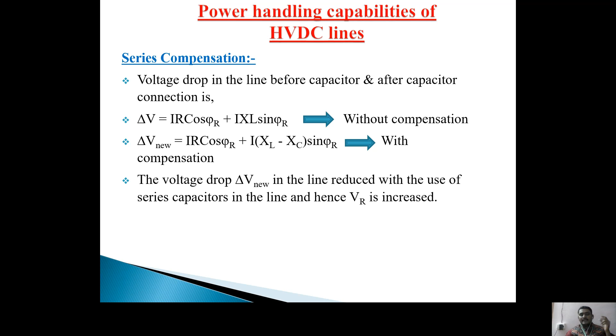With compensation, that is with the inclusion of the capacitor, the voltage drop changes to delta V new, which is equal to I R cos phi R plus I into (XL minus XC) sin phi R. This is the equation after inclusion of the capacitor into the line. Here the voltage drop delta V new in the line is reduced with the use of series capacitors, and hence VR is increased, and hence the receiving end voltage is increased.